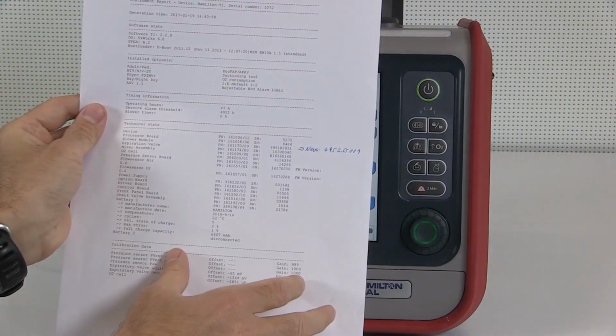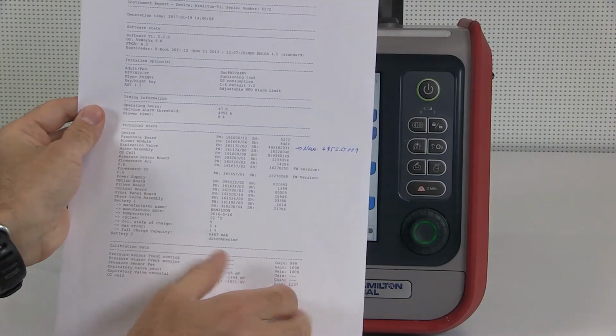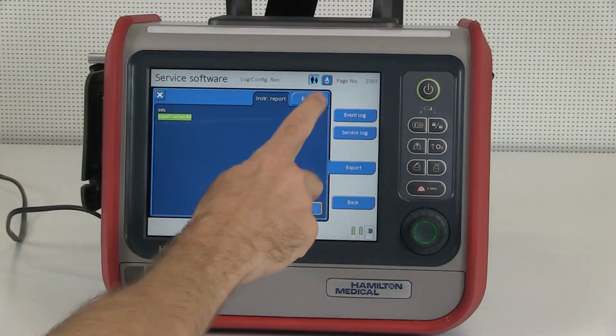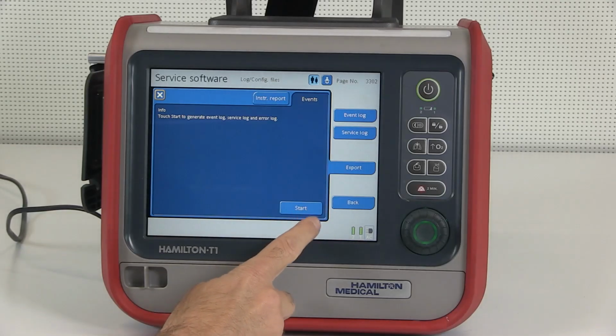This document gives you a detailed overview of the parts and software installed, as well as the calibration values of the ventilator unit. Export and archive this document each time you carry out preventive maintenance. Go back to Events and also export the log files if needed.